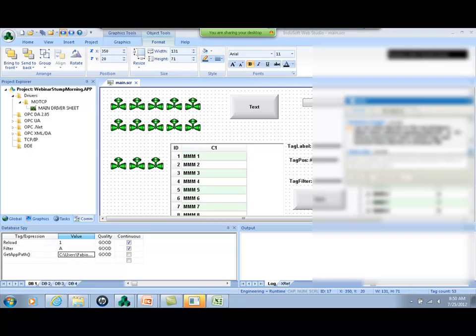So one question here, can we write directly to the tags database if you had an Excel macro that created the tags and inserted them directly to the database file? The driver worksheets can be created automatically as text files in the DVD from InduSoft. There is a file under documentation tech notes called InduSoft CNF files. It shows the format of the driver worksheets. So you can create a script to create the driver worksheets on the fly.